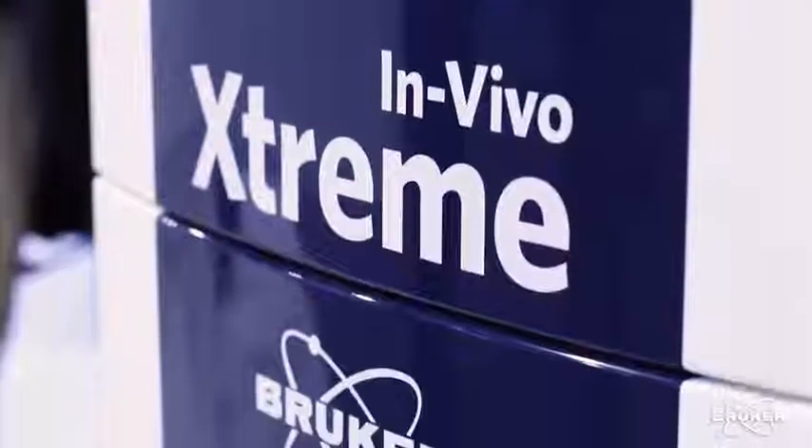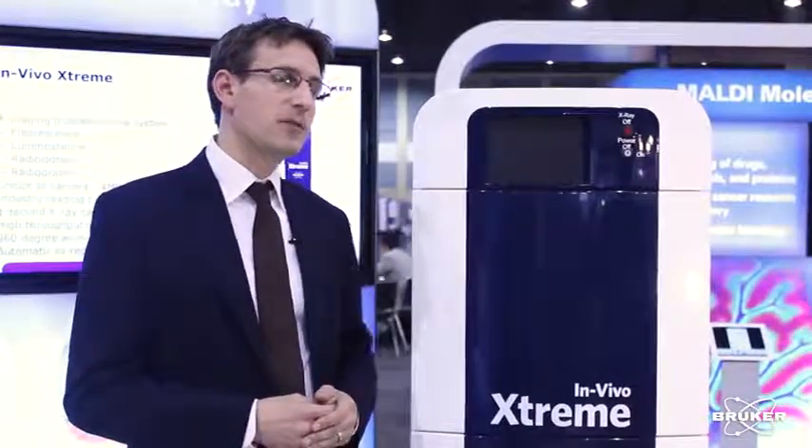The system itself, the Xtreme, is also equipped with 28 excitation filters that cover the whole range from the visible to the near-infrared light. With that, you are able to address roughly every fluorophore that is available in the market and that you produce yourself.